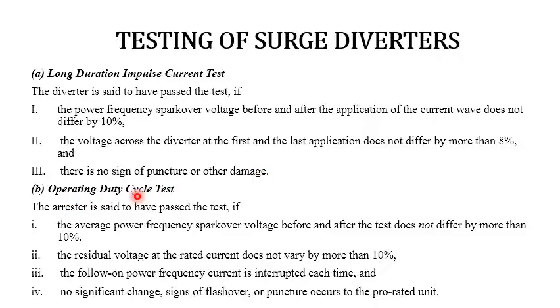Then we have the operating duty cycle test. This is conducted on units of arresters and gives better closeness to the actual conditions. The arrester is kept energized at its rated power frequency supply voltage. The impulse current wave is applied first at a phase angle of around 30 degrees from the AC voltage zero. If the power frequency follow-on current is not established, the angle at which the current wave is applied is advanced in steps of 10 degrees up to 90 degrees, or the peak position of the supply voltage wave, till the follow-on current is established.